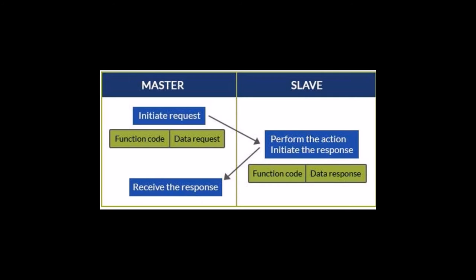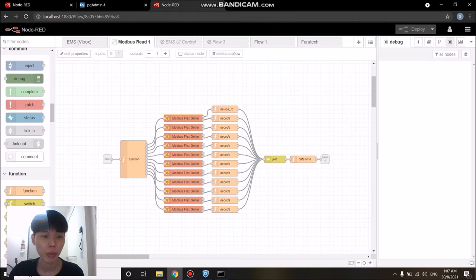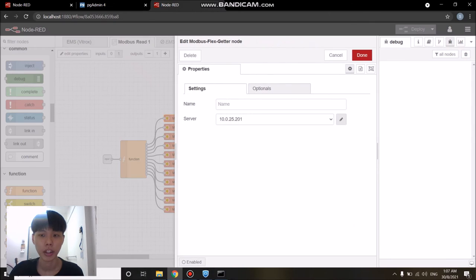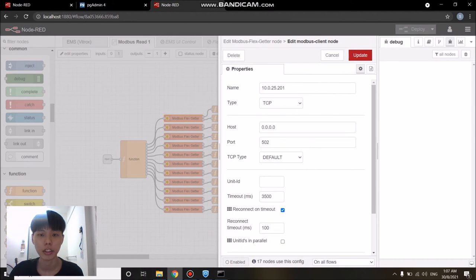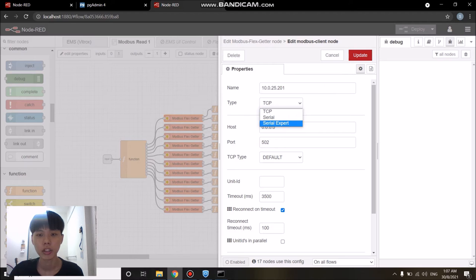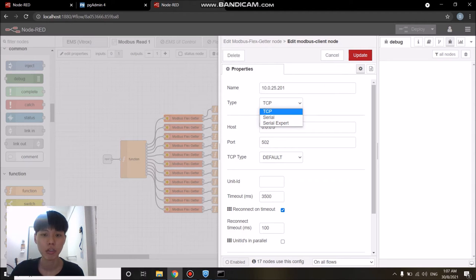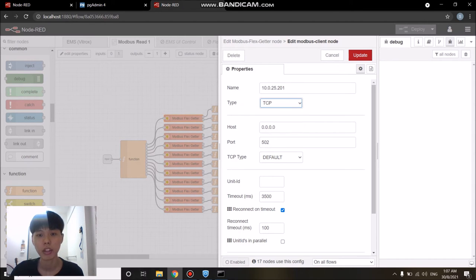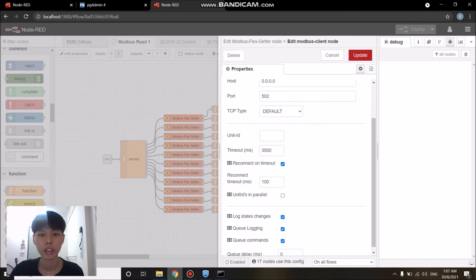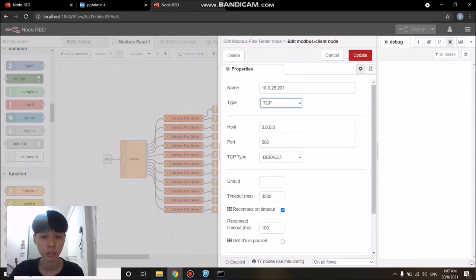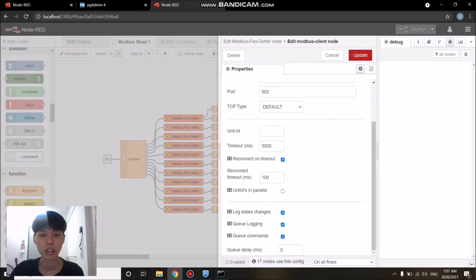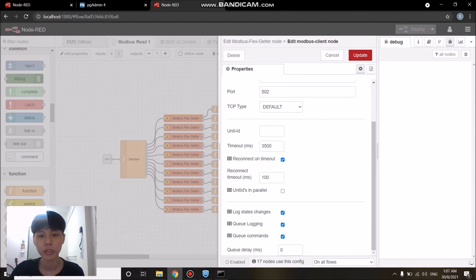Then the master will receive the response along with the data needed. If we open up the Modbus node, there are a few settings that we need to configure in order to use them such as the type of connection, TCP, serial or serial expert, the host of the server, the default port, the unit ID, timeouts, reconnect on timeouts and of course the unit ID in parallel.